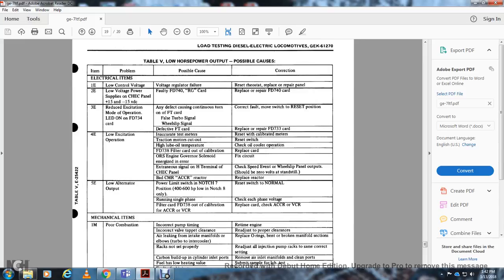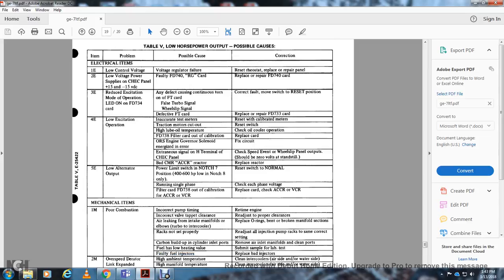All right, item 5E, lower alternator output. Reading the possible cause and then the correction. Power limit switch in the notch 7 position, 400 to 600 horsepower low in notch 8 only: reset the switch to normal. Running single phase: check each of the phase voltages. Filter card FD738 out of calibration, or the ACCR and the voltage current reactor: replace the ACCR and VCR.